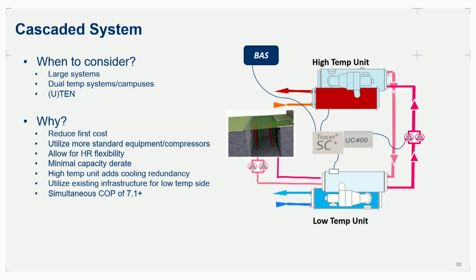You get these modular products where now you need 30, 40 modules, or you get these more specialty industrial type heat pumps that are really expensive. You see the dollars per ton on that, and it's astronomical compared to a more traditional chiller. So when you get into those larger sizes, suddenly that controls complexity becomes a drop in the bucket, and the equipment cost scales much, much better with size. Also, and I already touched on this, we're using more standard equipment.